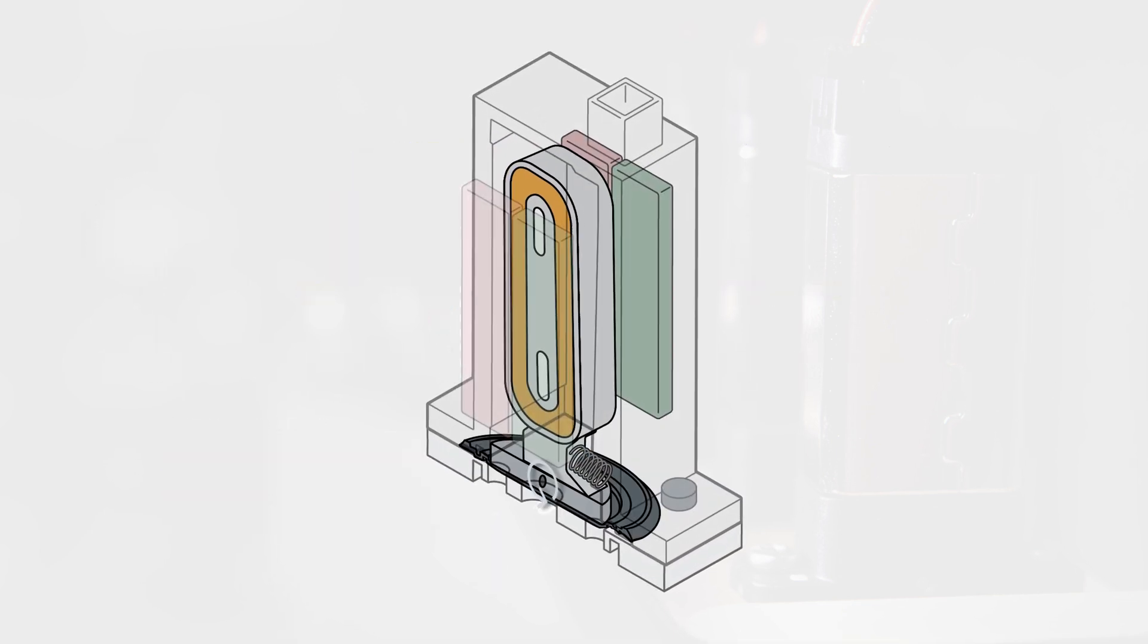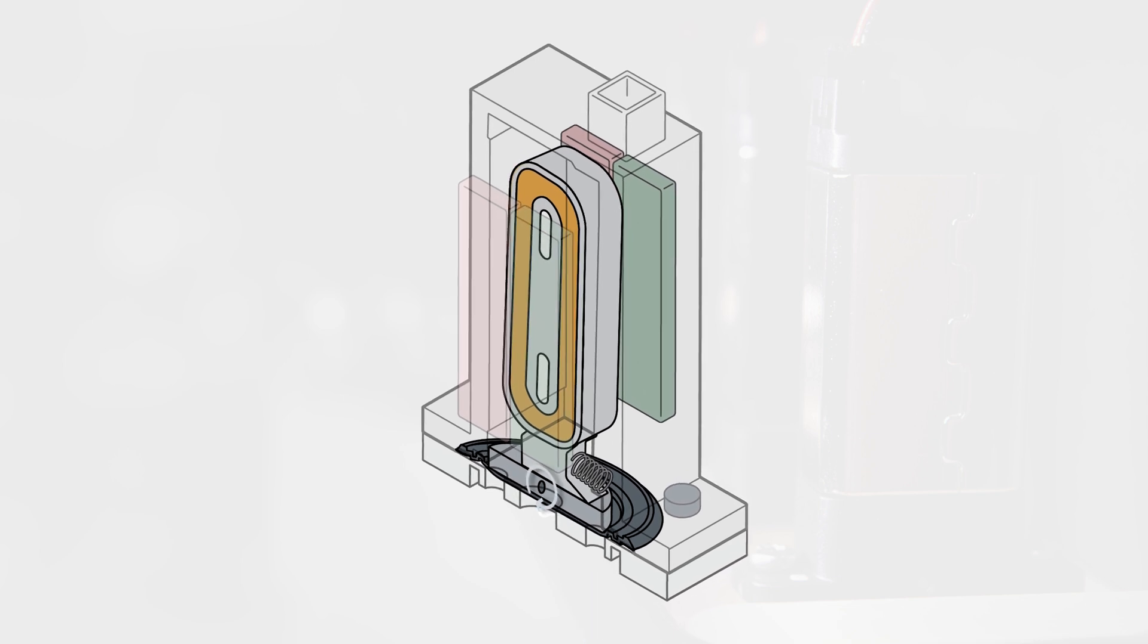The small internal volume of the valve ensures that only the smallest amount of expensive reagents remains unused.